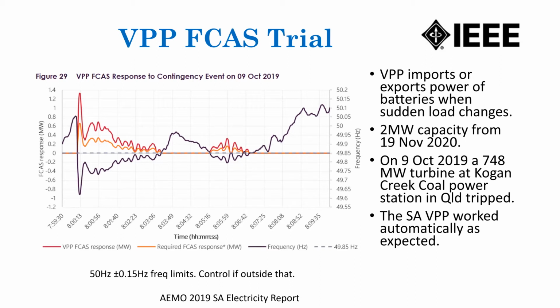On this graph, there's a limit of 150 millihertz on either side of the 50 hertz, and when the frequency at the trip, which was just up there, went outside the limits, then the battery, the virtual power plant, responded. This was what they expected the power plant to do, and it actually did more. So it worked much better than expected.